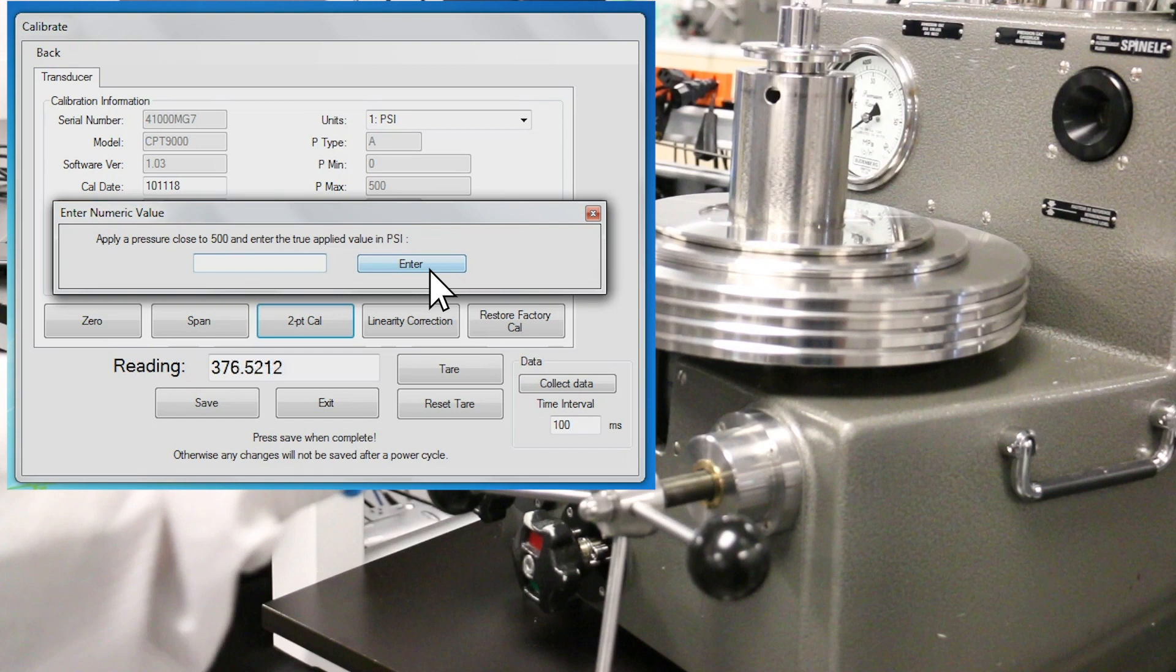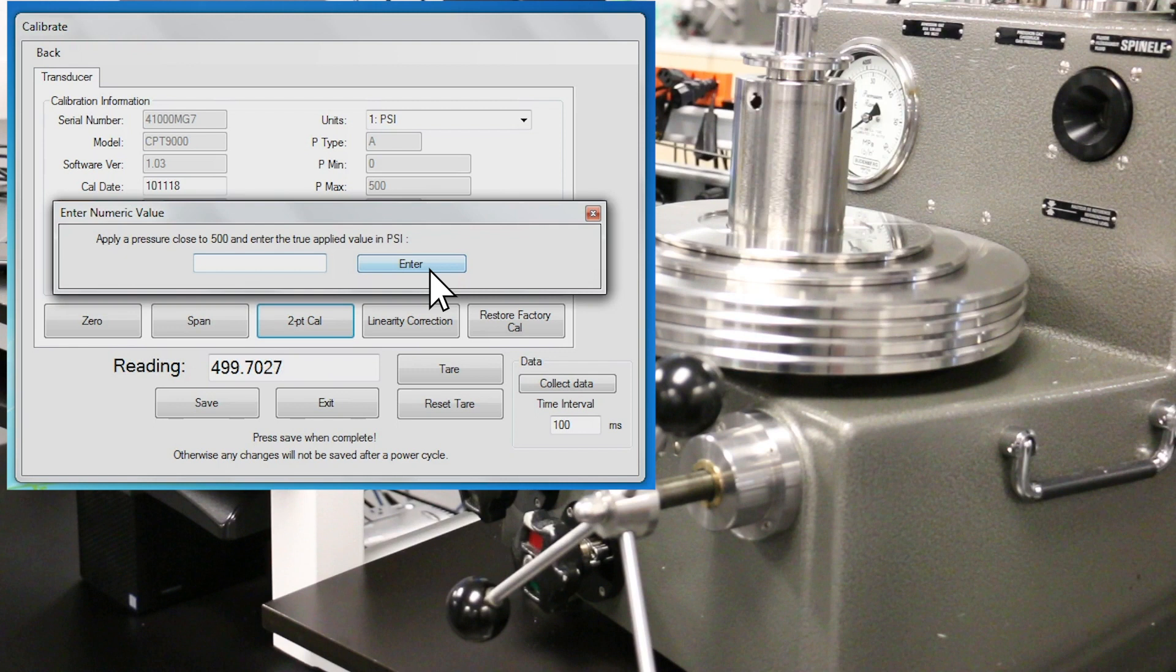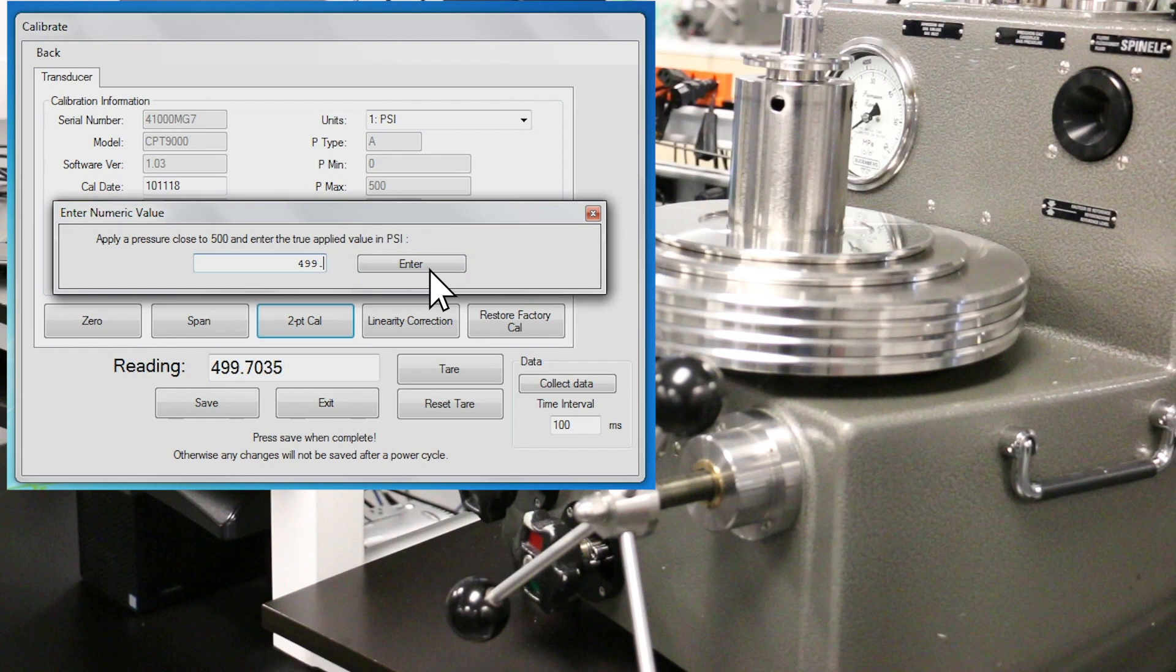Now, apply 500 PSIA using the deadweight tester. After the pressure has stabilized, compare the reading with the pressure being generated by the deadweight tester and record if as-found data is needed. Type the pressure applied by the deadweight tester and press the enter button. This sets the span value.